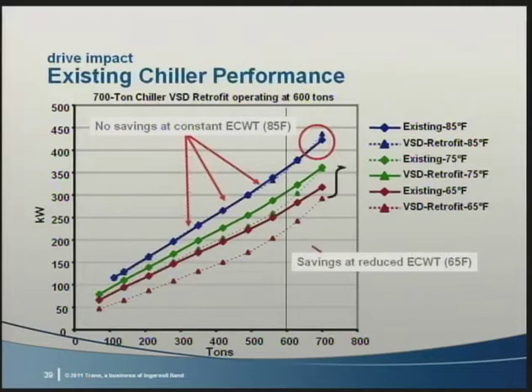However, there are kW savings available when the condenser water temperature, that is the lift, is reduced. As you can see here, operating at reduced load and lift provides substantial savings, on the magnitude of 35% when operating at 600 tons. Now let's look at a couple other considerations. So what issues should we consider when examining the economics of retrofitting with a drive?